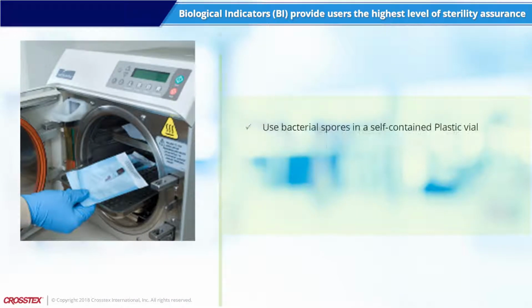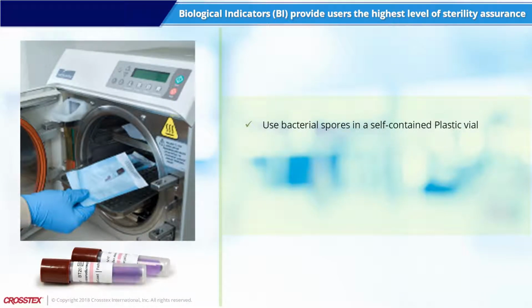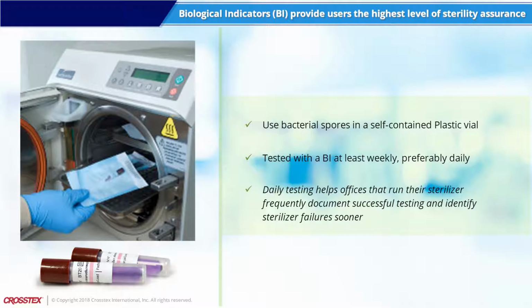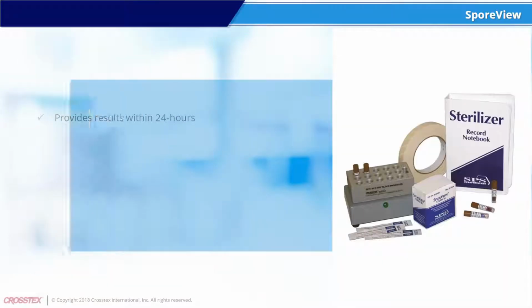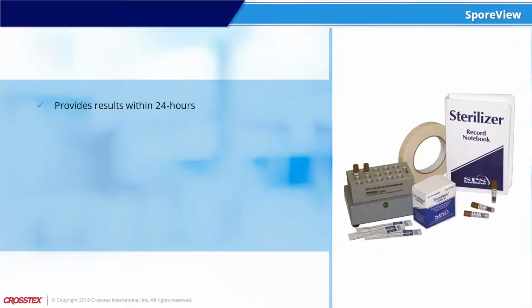Biological indicators, BI, provide users the highest level of sterility assurance and contain bacterial spores in a self-contained plastic vial. Sterilizers should be tested with a BI at least weekly, preferably daily. Daily testing helps offices that run their sterilizer frequently document successful testing and identify sterilizer failures sooner. The Spore View in-office biological indicator provides customers with test results in 24 hours.